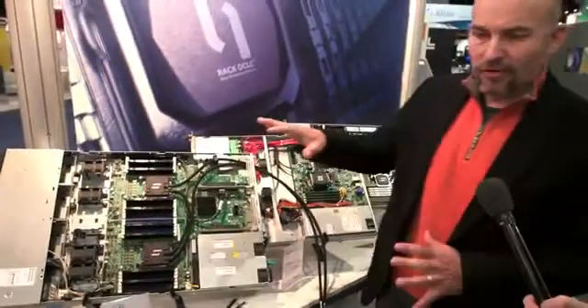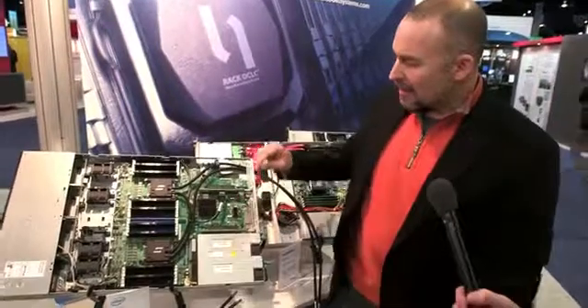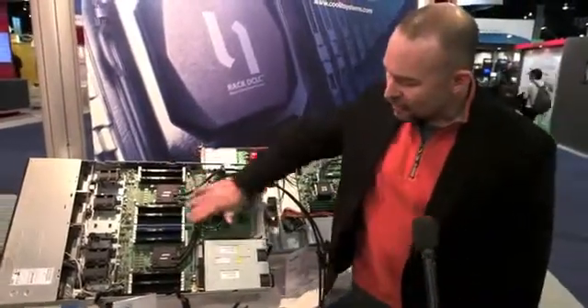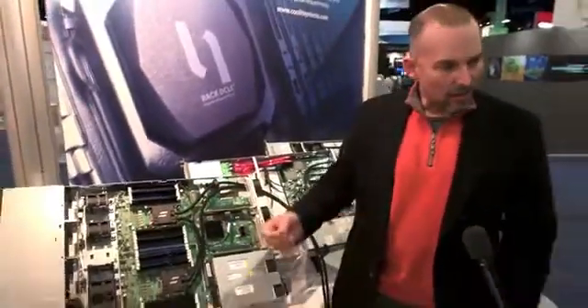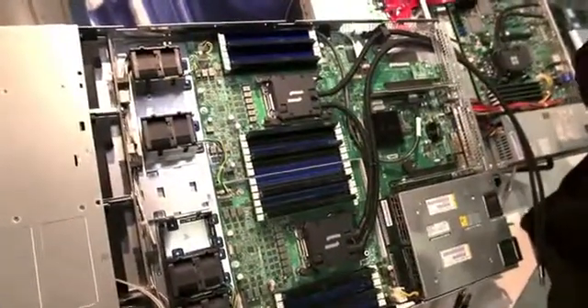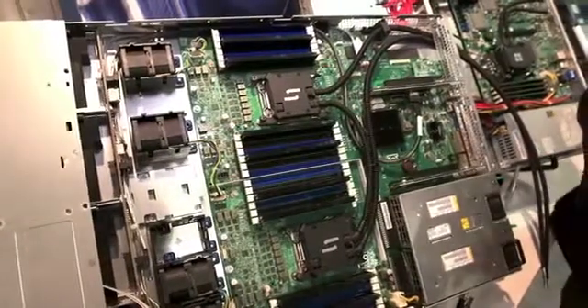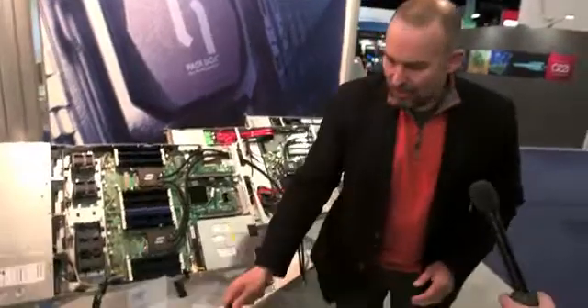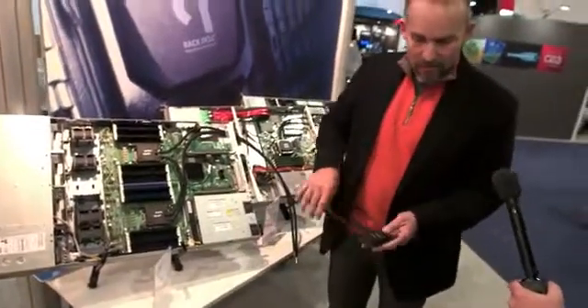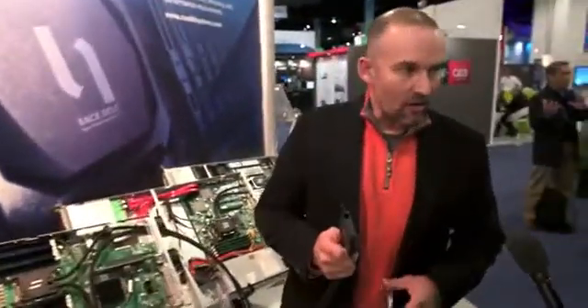Well, that's terrific, things got some momentum here. Why don't you show us what you got in the booth? This year what's new for us is we've moved to a centralized pumping scheme. We've created a very low profile cold plate, that's the copper plate that has very small micro channels built into the system. It transfers the heat from the processor directly into the liquid. So it gives us the ability, since there's no pump in here anymore, to go to a very narrow construction. It's only 15 millimeters tall.